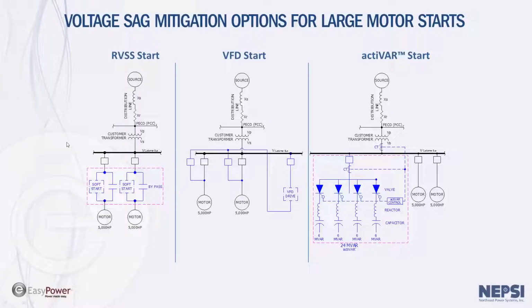So when the cross-the-line motor start does not work, typically the other two options that are considered are reduced voltage soft start and the VFD starter. The reduced voltage soft start is by far the most favorable option, as it is the most cost effective. A reduced voltage soft start has a cost of about $40,000, and therefore it is typically what is looked at when looking to mitigate voltage sags associated with a large motor start.